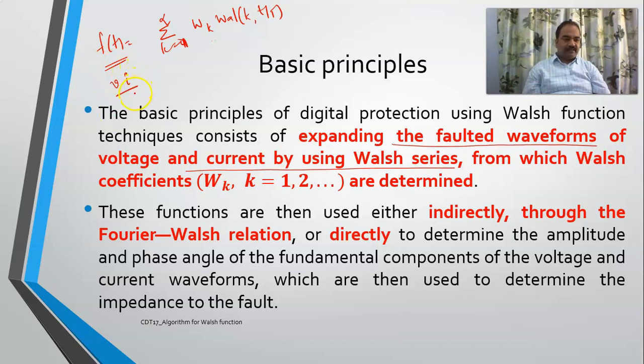Any signal, any faulted waveform, if you want to analyze, first of all, you will be representing it in terms of Walsh series. And these functions are then used either directly or indirectly through the Fourier-Walsh relation. Or you can directly employ the Fourier-Walsh series also to determine the phasor of the fundamental component and also harmonics. Thereby, you can design which filters you want to employ.